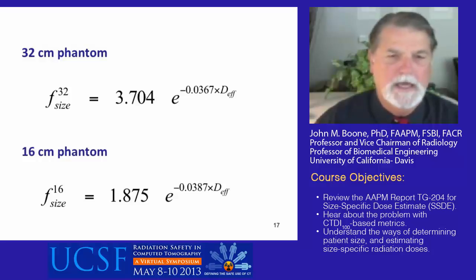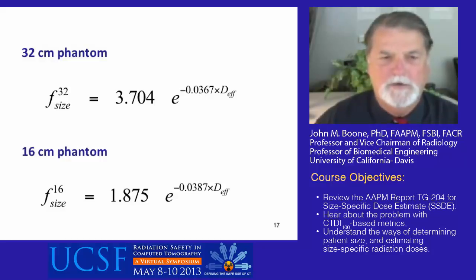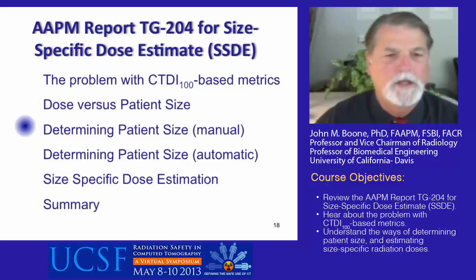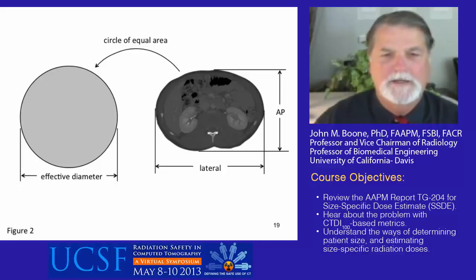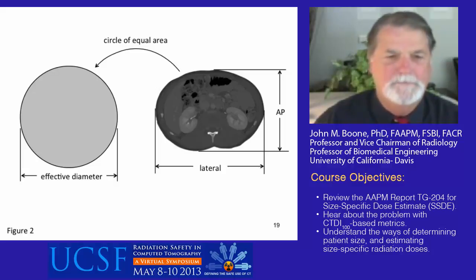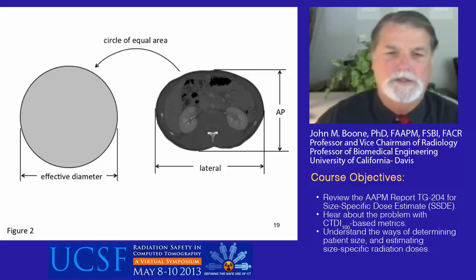Because it's analytic, the exponential function makes it easy for software vendors to code once you know the effective diameter or the water-equivalent diameter. In terms of determining patient size manually, a CT axial image has a certain area, and we treat the effective diameter as a circle with the equivalent area. Other parameters we can use are the AP dimension, the lateral dimension, and the sum of these two values.